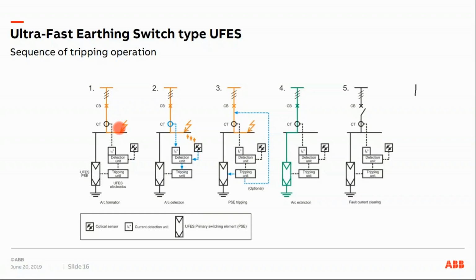If a specific criteria or condition for tripping is fulfilled, the UFES electronic issues a trip signal to the three primary switching elements, which then establish a three-phase metallic short circuit at the point of installation. As this short circuit is of considerably lower impedance, the fault current commutates from the arc to the defined short circuit created by the PSE, causing the arc fault voltage to break down and the arc to be extinguished almost immediately after tripping. And the rest is then cleared by the upstream circuit breaker again.